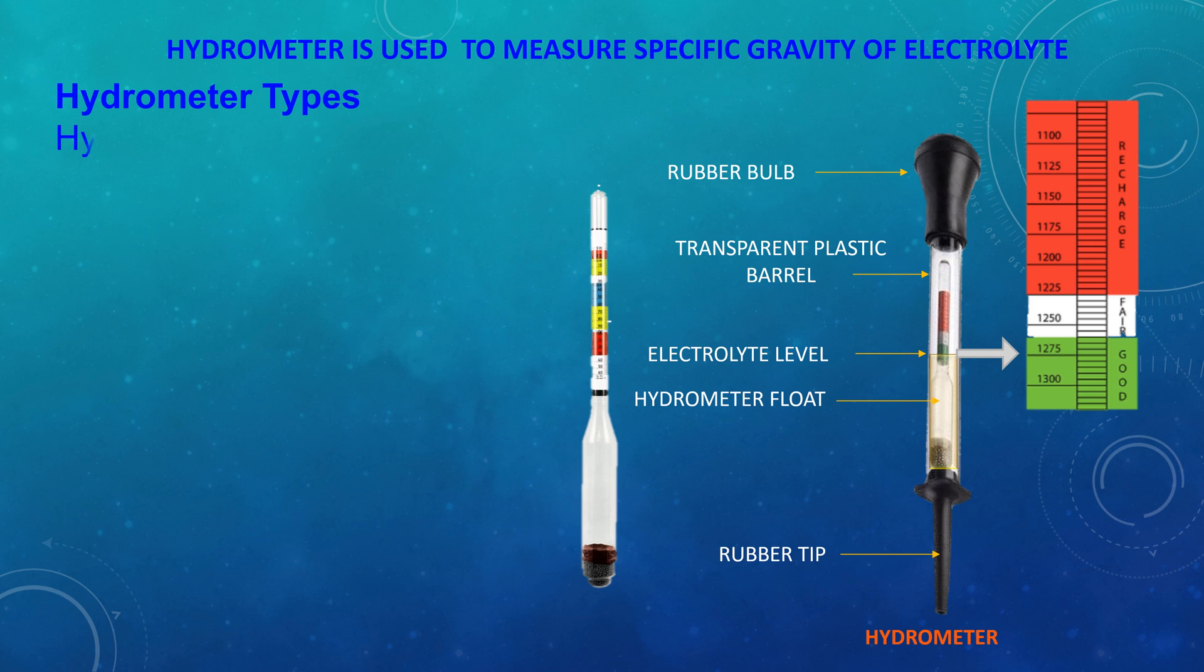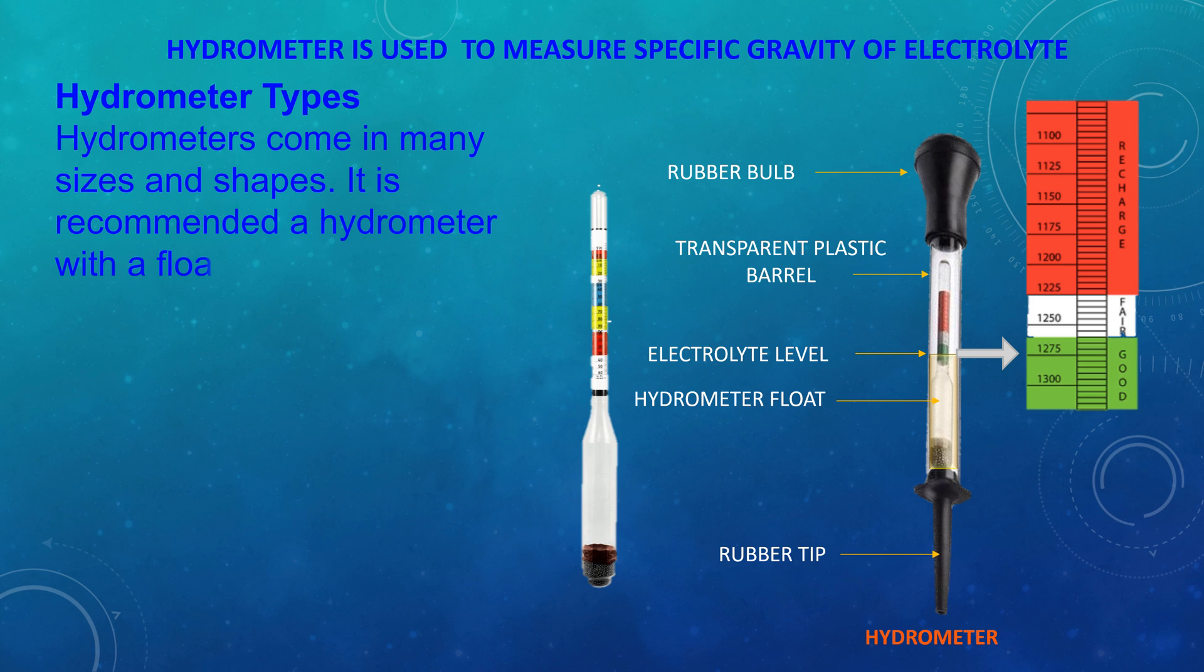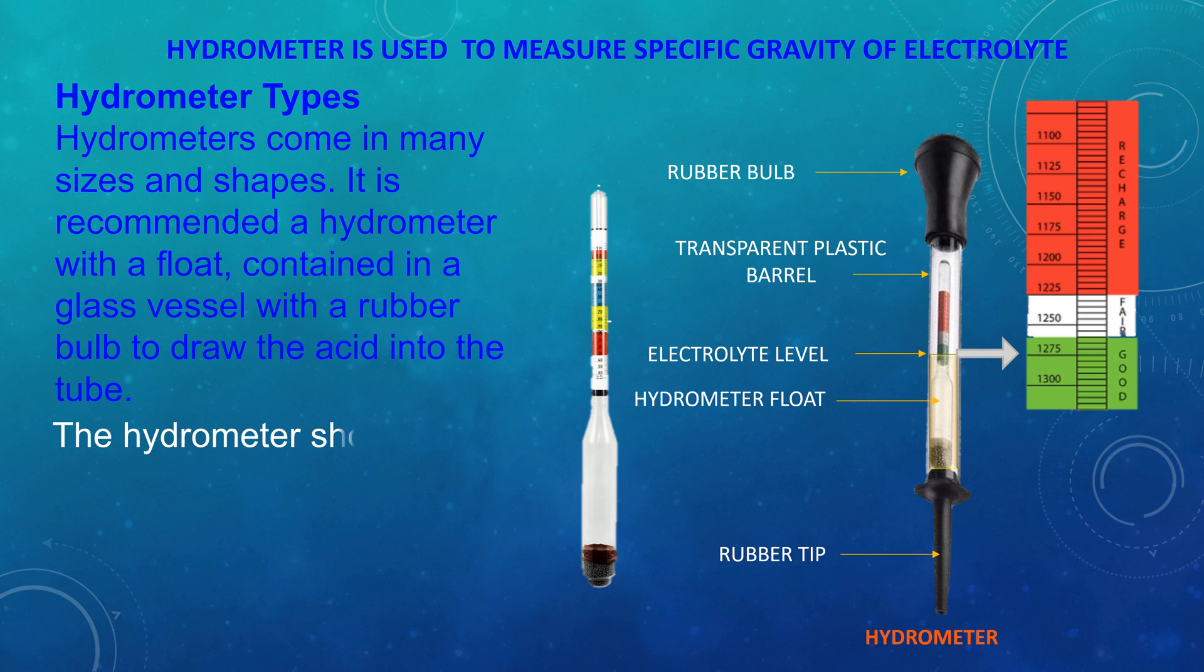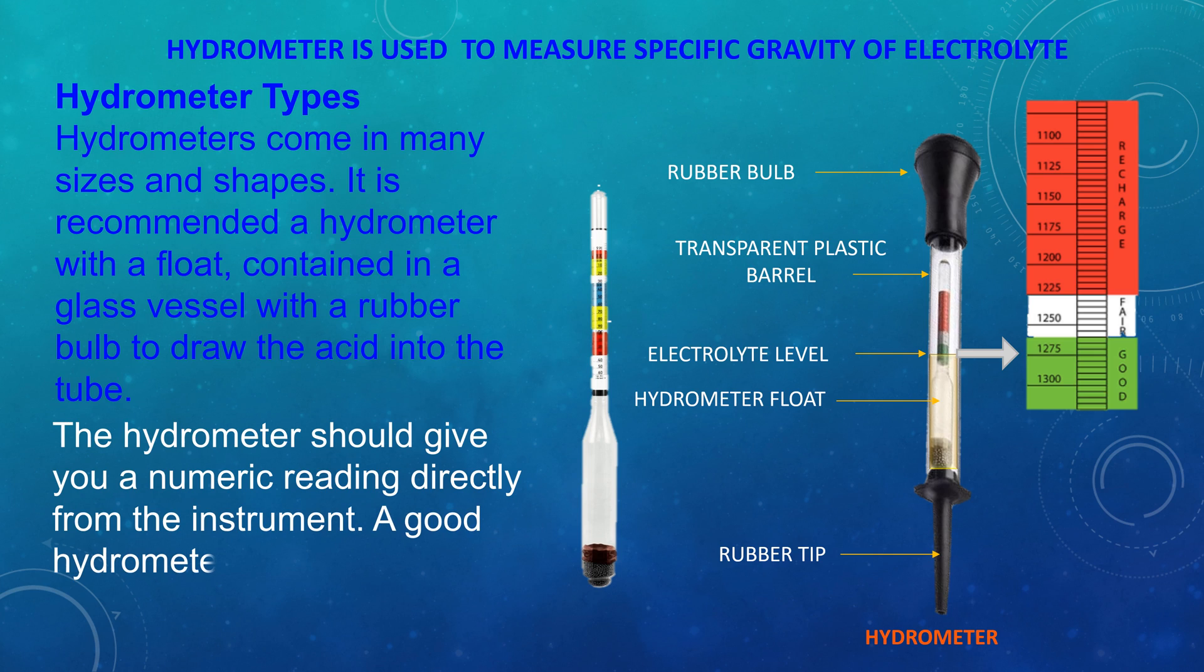Hydrometer types: Hydrometers come in many sizes and shapes. It is recommended a hydrometer with a float contained in a glass vessel with a rubber bulb to draw the acid into the tube. The hydrometer should give us a numeric reading directly from the instrument. A good hydrometer is accurate to plus minus 0.005 points. So, 1.270 could read from 1.265 to 1.275.